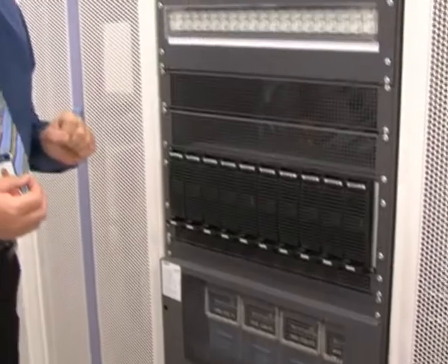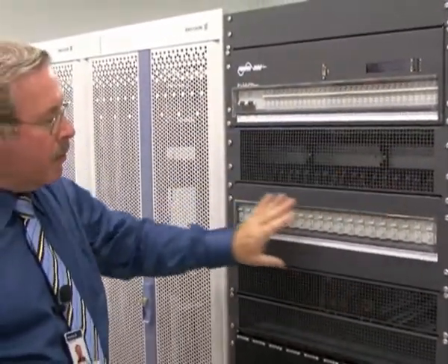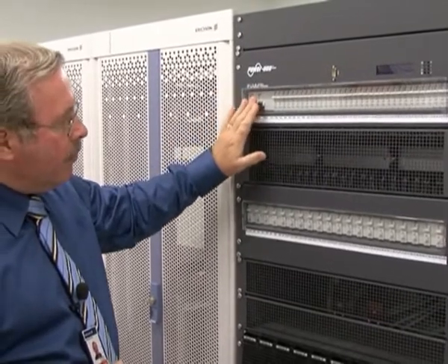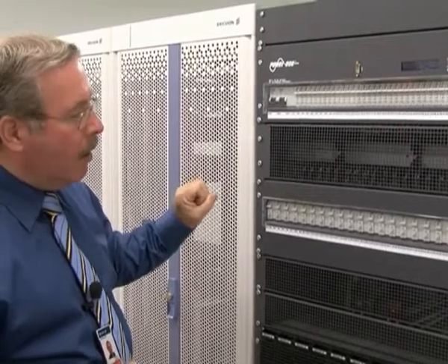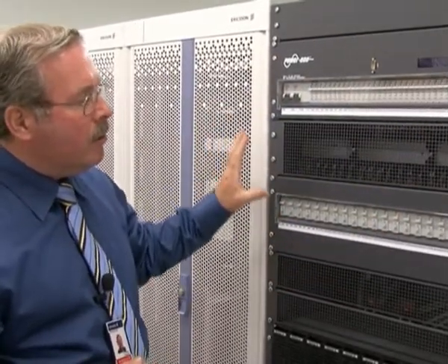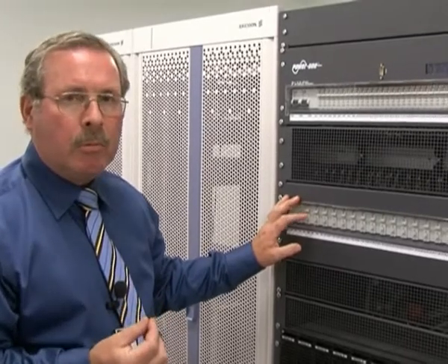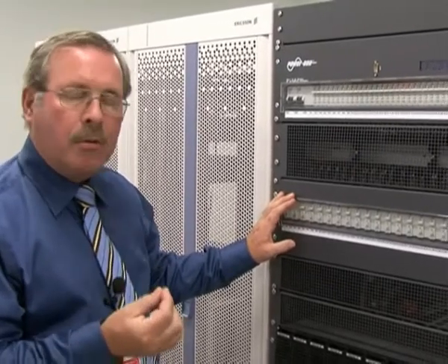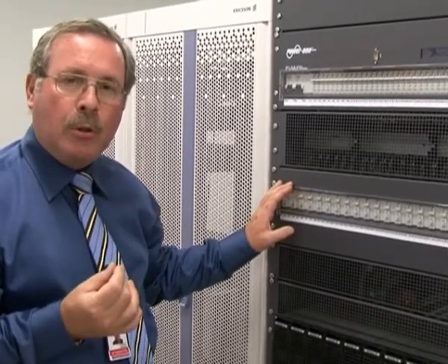So this external source is being fed via these breakers. We have got 2 banks of batteries, power breakers, and we are feeding external equipment. However, this particular example is configured to have a low ohmic distribution. This actually is not so suitable for a switch or an exchange. To do that, we need a power distribution unit, and we have housed these in another cabinet.